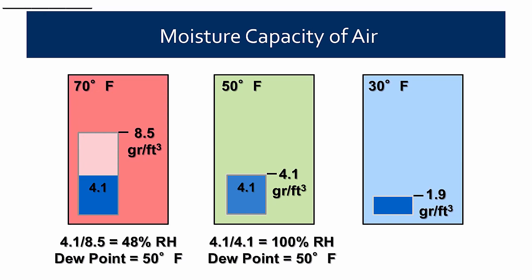The dew point is 50 degrees in this case. By looking at the middle diagram, it's easy to understand why — at 50 degrees, air can only hold 4.1 grains, so it's saturated at 100% relative humidity. At 70 degrees it's 48% relative humidity; at 50 degrees it's 100%. That's pointing to the fact that you really don't want to look at relative humidity, because 100% sounds like a lot, but it's still the same amount of moisture — 4.1 grains per cubic foot.